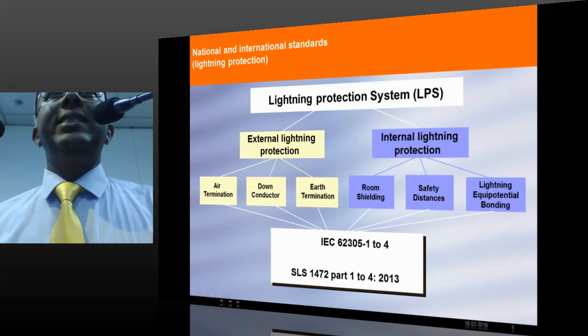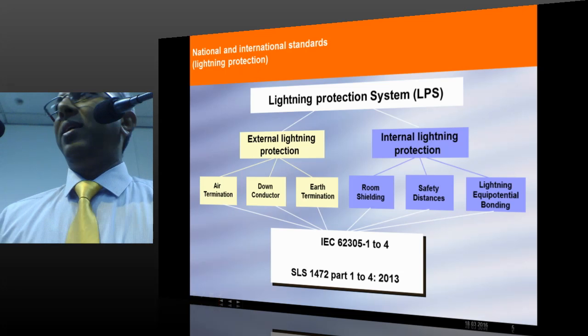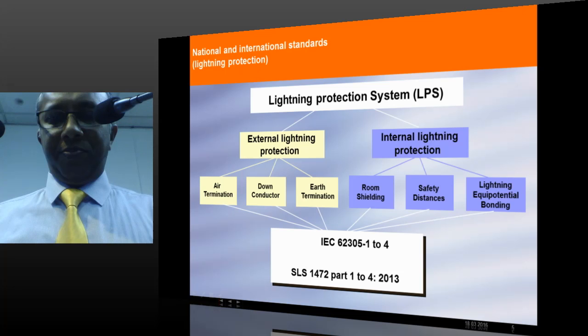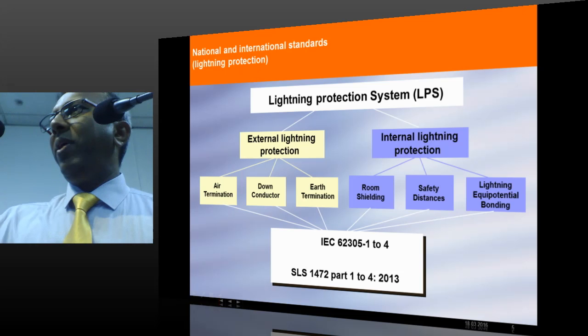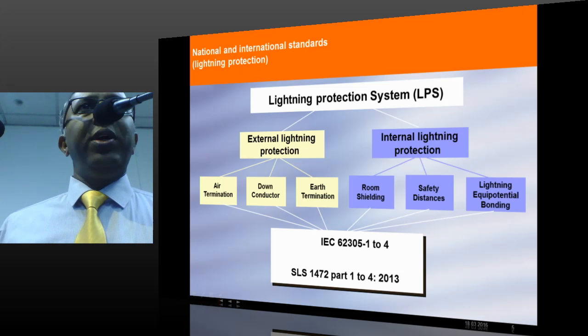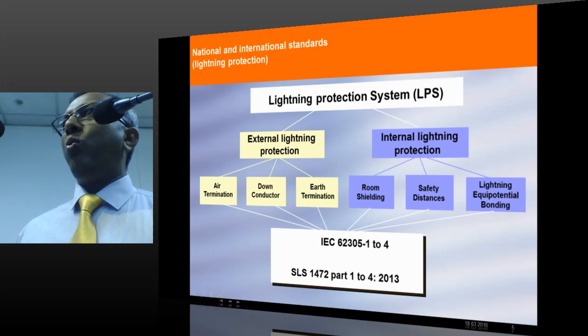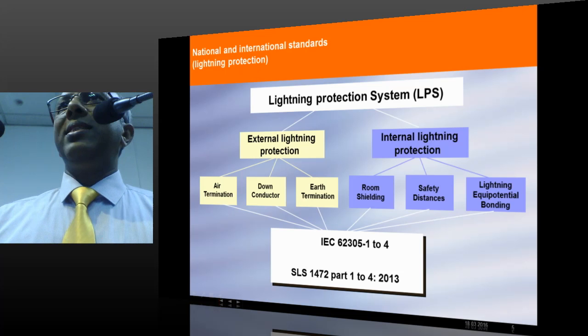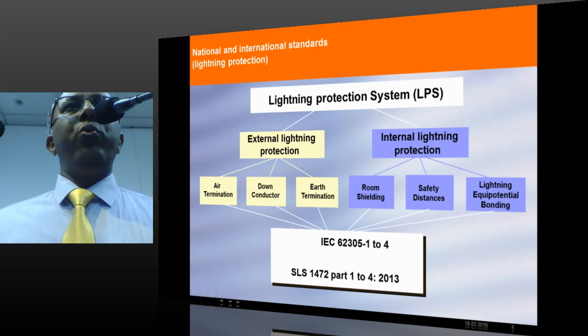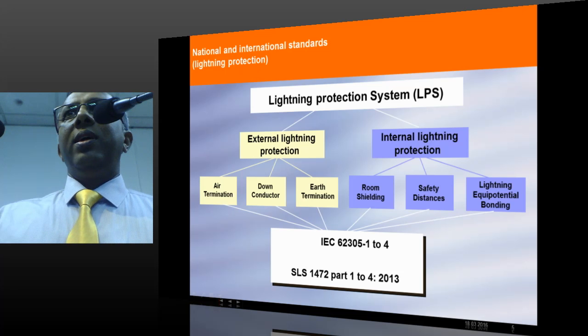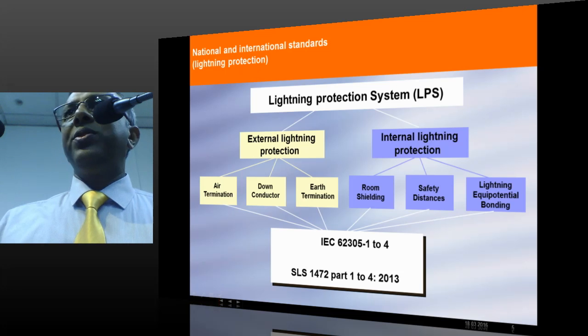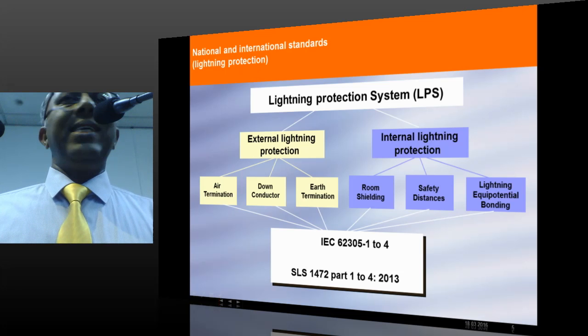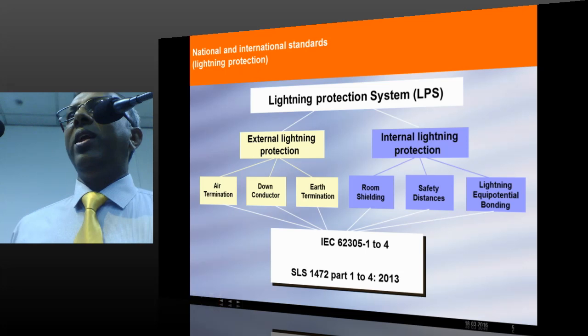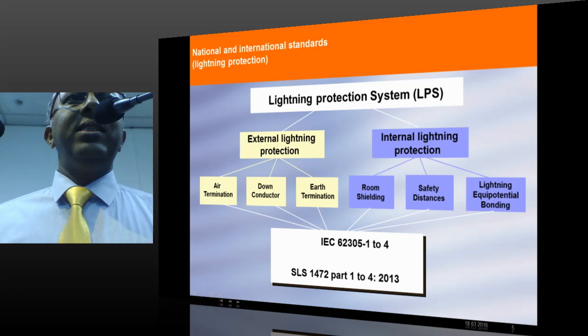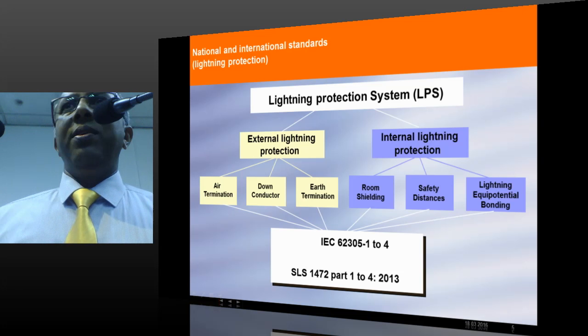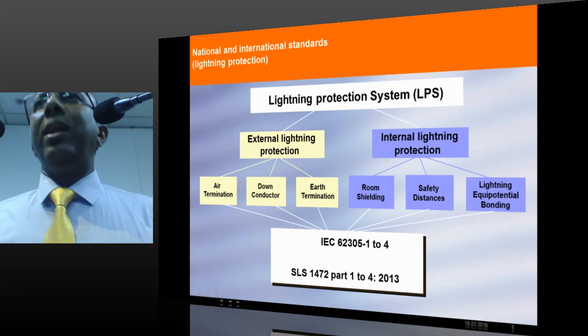So if we can achieve a good equipotentialization, all our equipments will be safe. And now the biggest advantage as a Sri Lankan citizen, the biggest advantage for you is SLS 1472 part 1 to 4 explains this subject in a very good way. Why SLS is important for you is not only the technical part, there is a commercial implication. If somebody wants to have the knowledge of IEC, and if you go and buy an IEC standard, it's very expensive. Whereas SLS standards you can buy at a nominal charge.